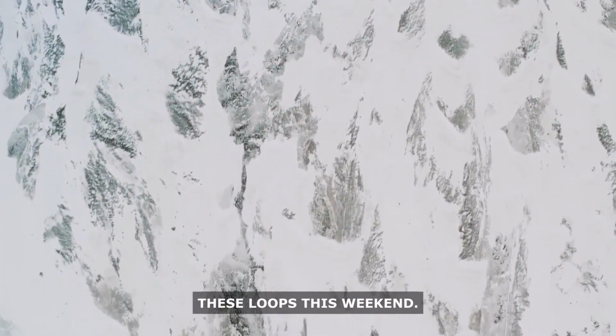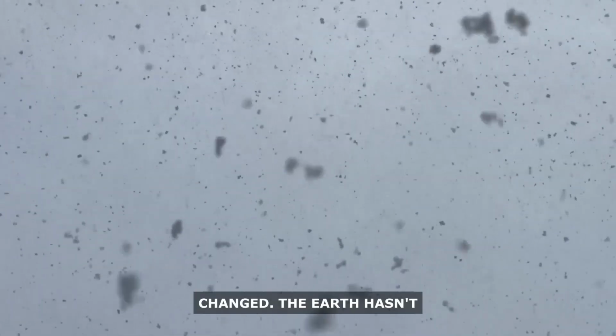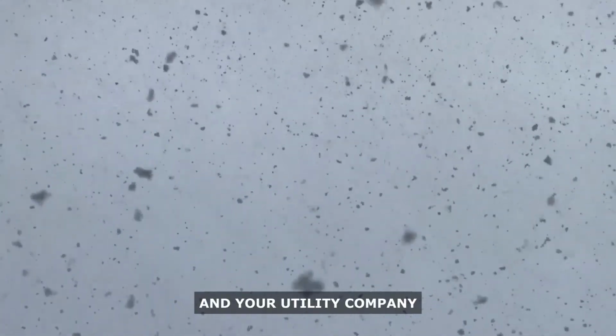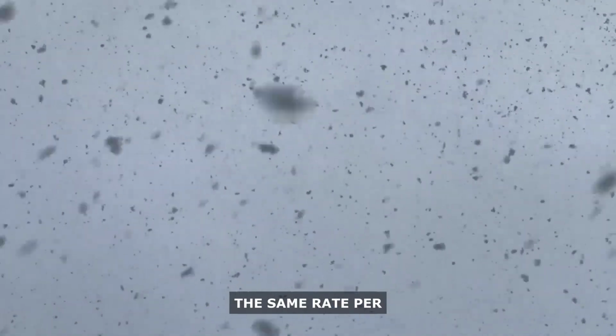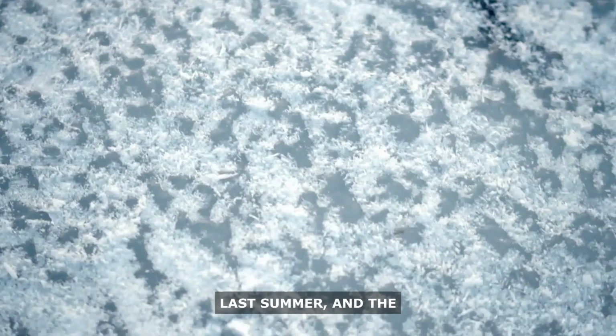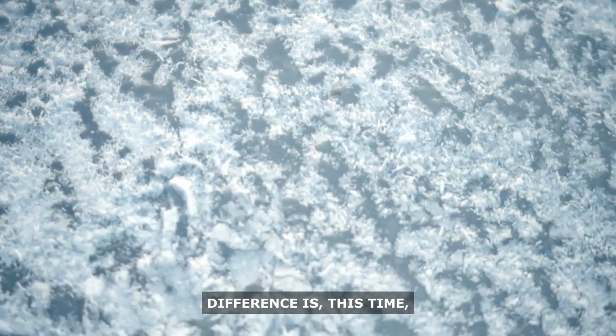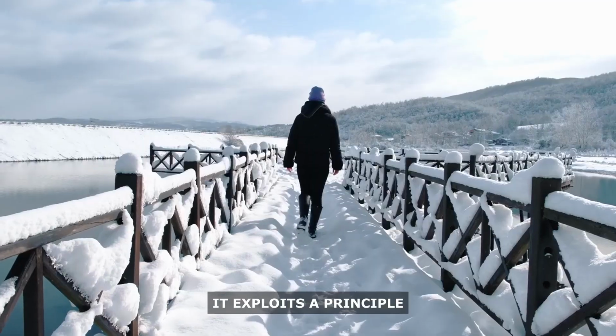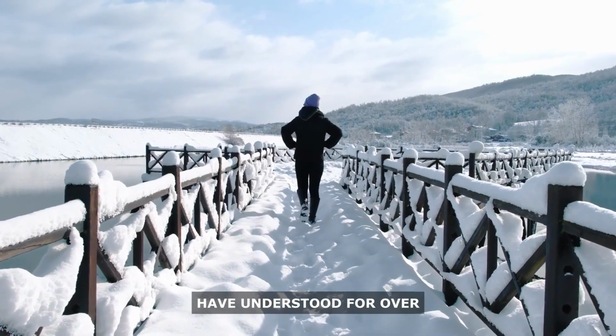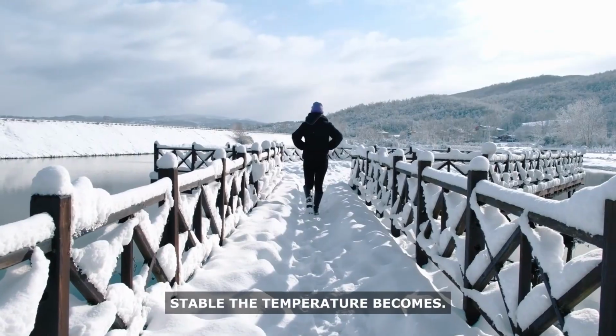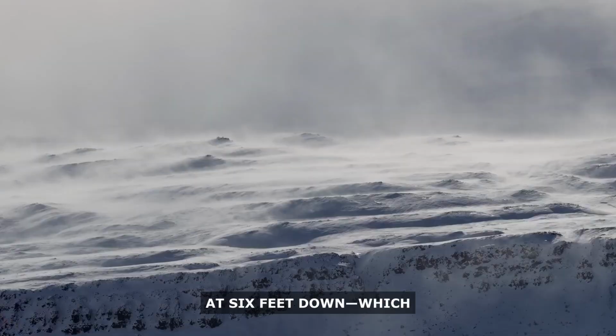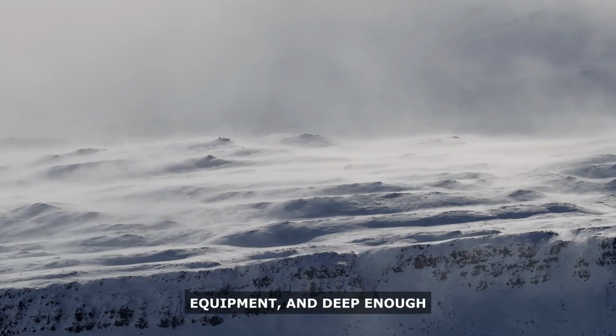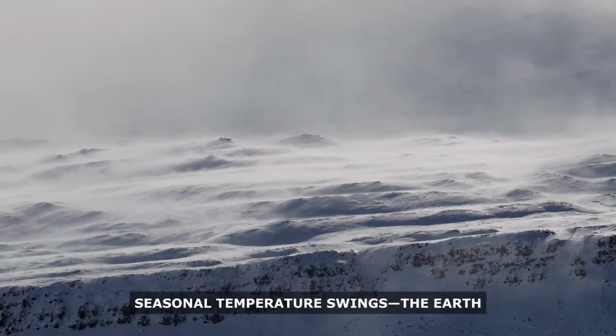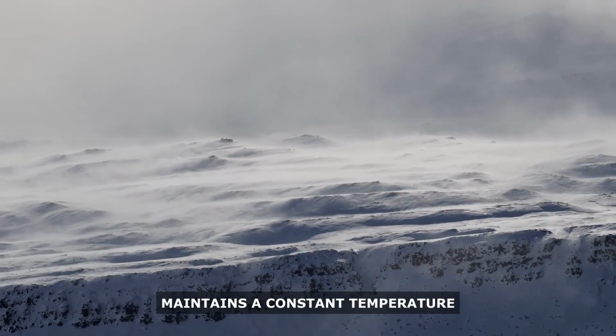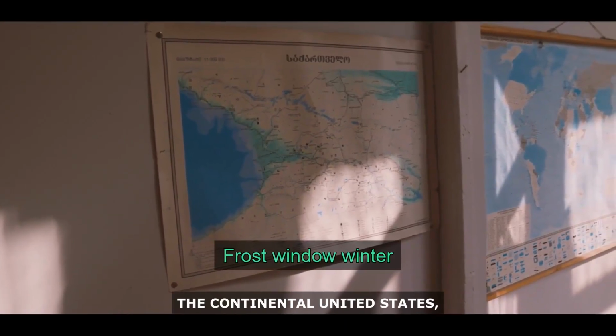The buried coil system works because it exploits a principle that geologists and engineers have understood for over a century. The deeper you go, the more stable the temperature becomes. At 6 feet down, which is shallow enough that you don't need heavy equipment, and deep enough that you're past the seasonal temperature swings, the Earth maintains a constant temperature band. In most of the continental United States, that band sits between 50 and 58 degrees Fahrenheit. Year-round, summer and winter, it doesn't move. Your air conditioner, by contrast, has to work frantically to push heat out of your house against an outdoor temperature that's sometimes 40 degrees hotter than the temperature that's already sitting right under your yard. That's thermodynamic waste. That's where your money goes.